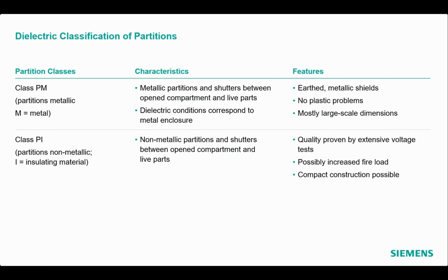The PM class is characterized by metallic partitions and shutters between live parts and opened compartments, and these metallic barriers are earthed. The basic features include the earthed metallic shields surrounding the opened or accessible compartments. Because metals are used, there are no problems concerning plastic. At the same time, this could lead to bigger dimensions.